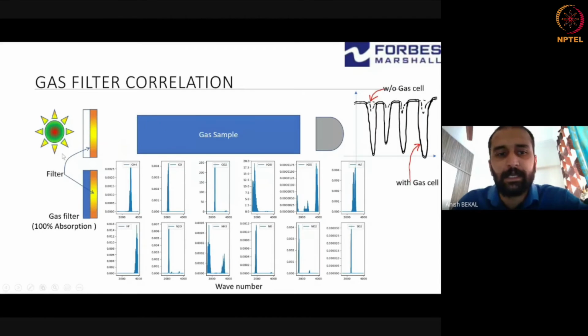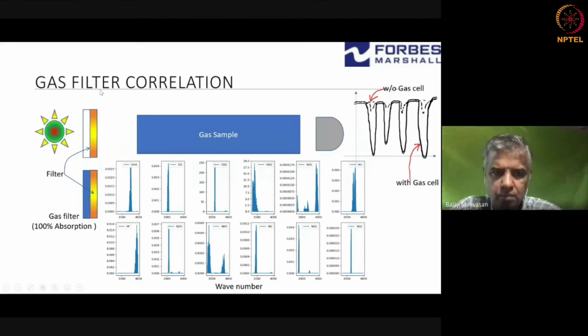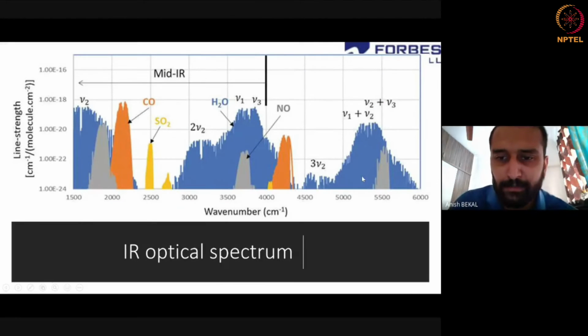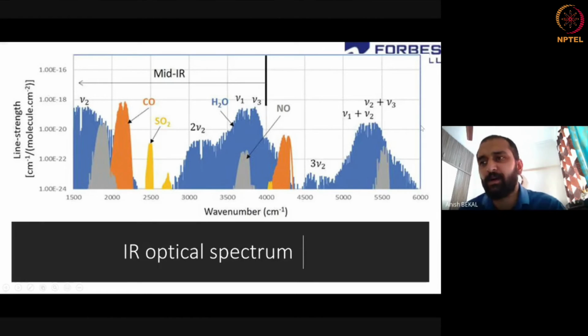Broadband sources use something called gas filter correlation. So it's highly dependent on what technology exists for what you want to do. If that problem doesn't exist, you could go for a quantum cascade laser running in the mid-IR region, or for a UV region broadband approach. You would never want to go to the broadband approach, but sometimes the technology only exists in that region.